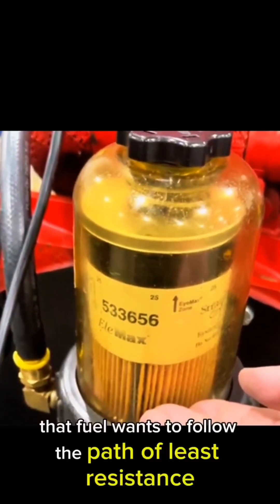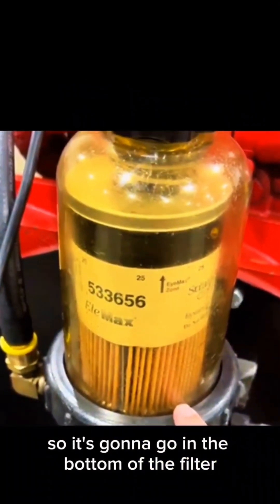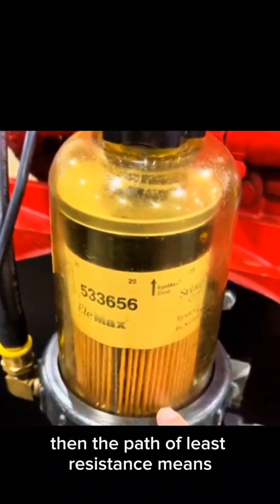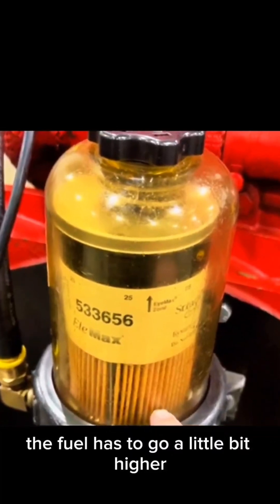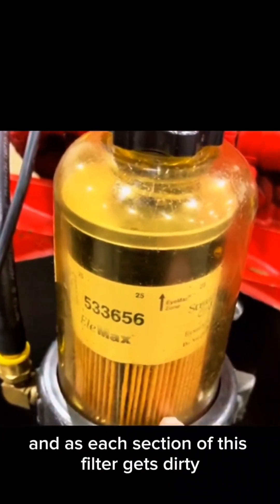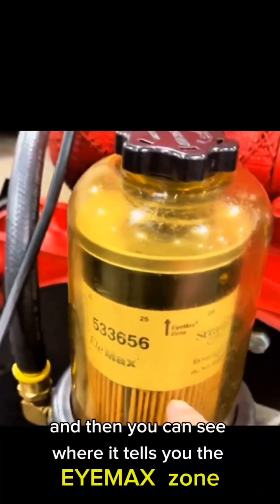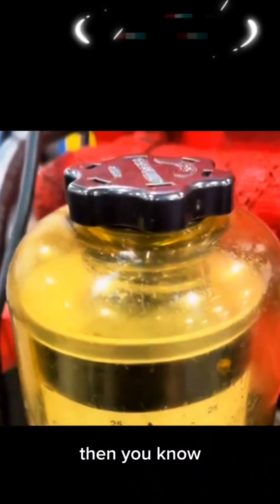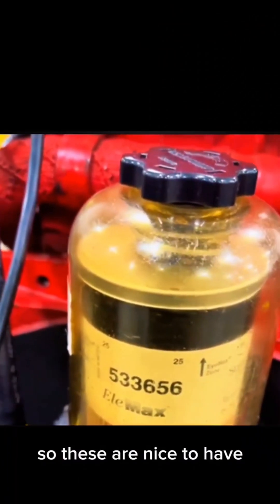The fuel wants to follow the path of least resistance, so it's going to go in the bottom of the filter. But once the bottom of that filter starts collecting too much contamination, the path of least resistance means the fuel has to go a little bit higher to go through the filter. As each section of this filter gets dirty, the fuel level is going to rise inside of this housing, and then you can see where it tells you the EyeMax zone — basically, once it gets up into this area, it's time to change that filter because it's getting too clogged up.